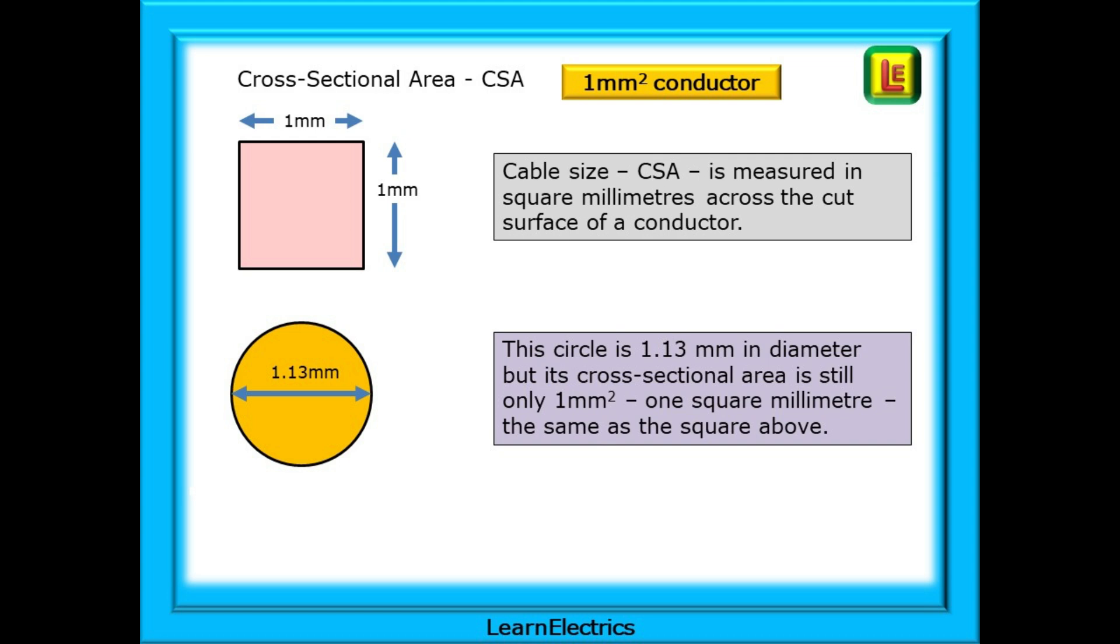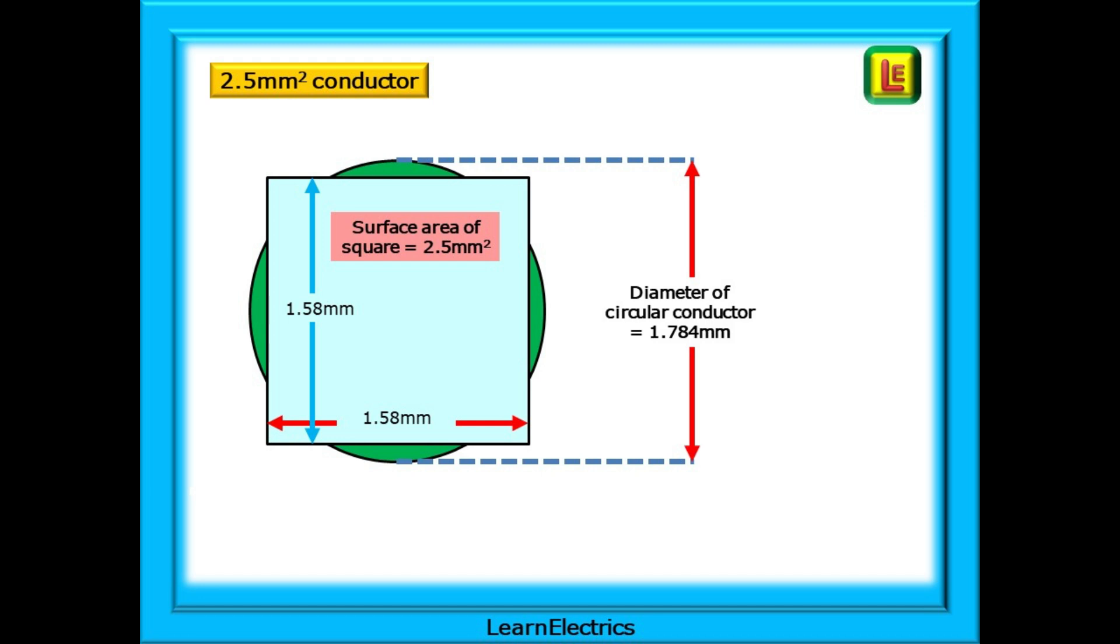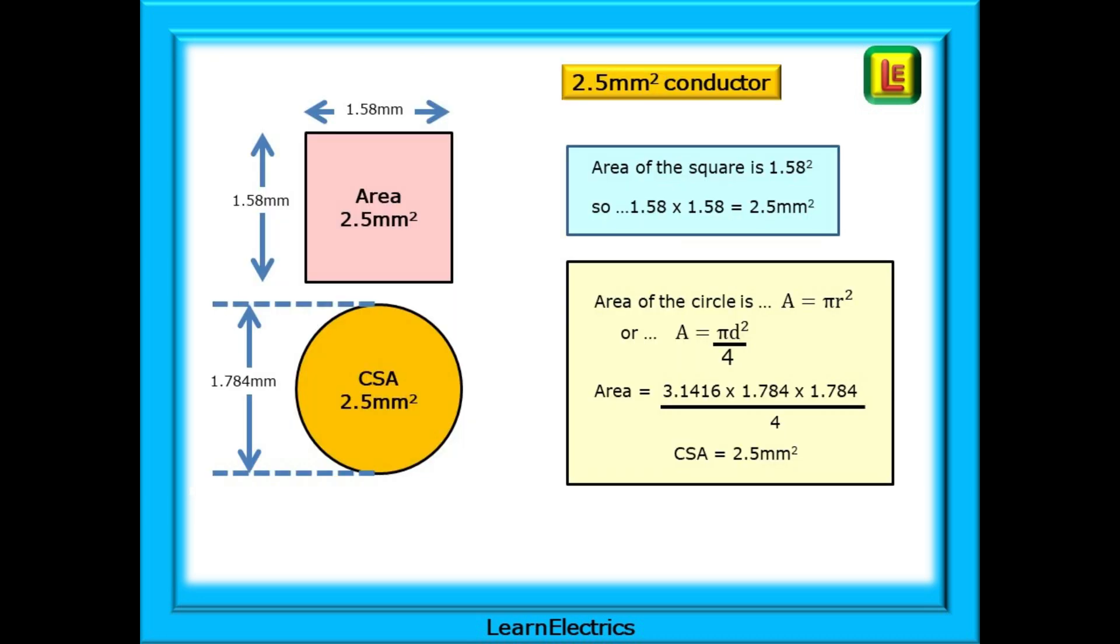The same area or CSA as the square above it. Look at this 2.5 square millimeter conductor. Nothing here relates to 2.5 millimeters. If it was a square conductor it would have sides of length 1.58 millimeters and if it was round as we normally expect then the diameter is 1.784 millimeters. Let's do the maths on this. The area of the square conductor is 1.58 squared, or 1.58 multiplied by 1.58. Try this in your calculator. The answer is 2.5 square millimeters when rounded up.